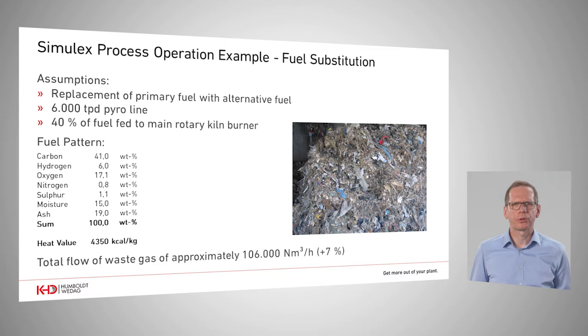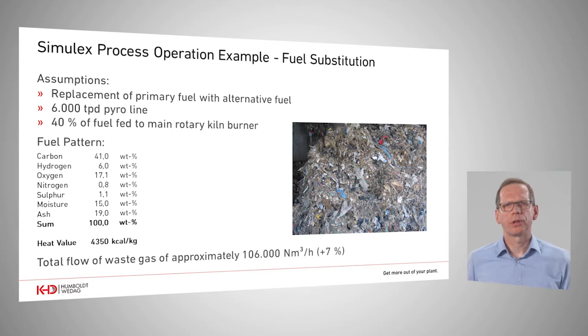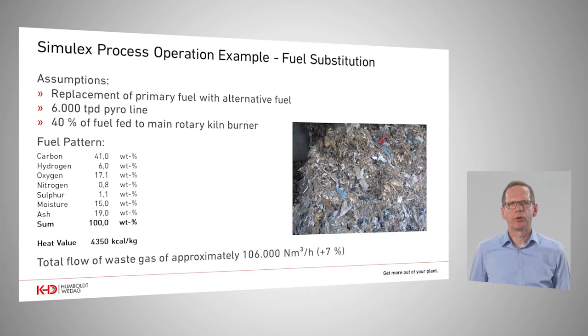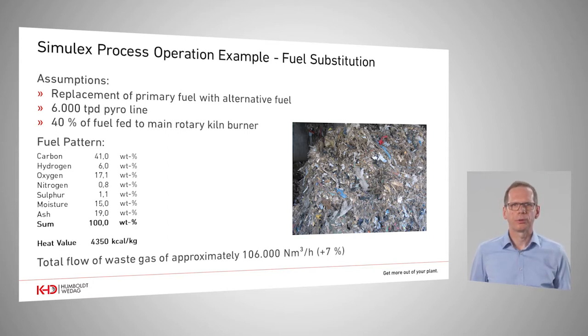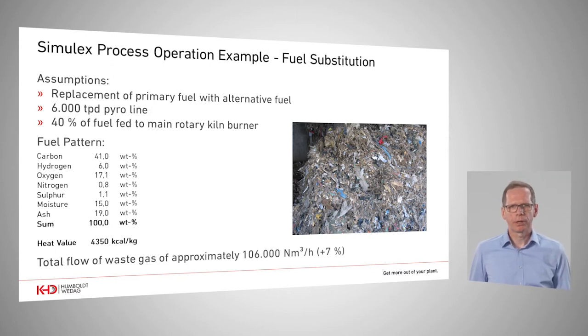Considering the fuel composition as shown on the slide, we would have a 7% higher waste gas flow. Although 7% is not too much, we still need to verify and assess what impact this change would have on the entire production process. Moreover, due to larger particle sizes in alternative fuels, we might even experience a shift of the burning zone and thus need to fire more alternative fuel to ensure that our product quality remains the same. This is where we can utilize Simulex to assess our plant changes without risking any negative impact on our actual production.